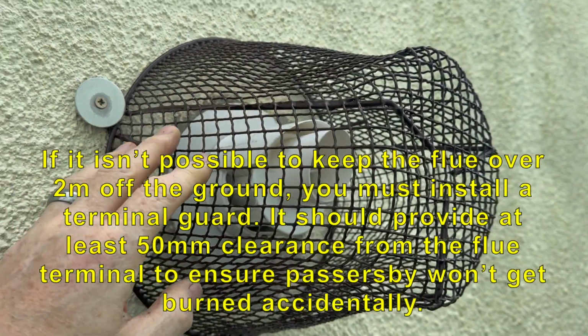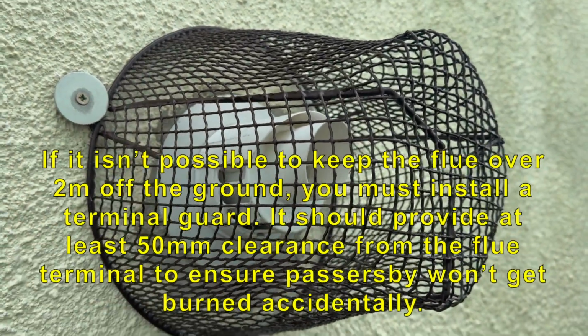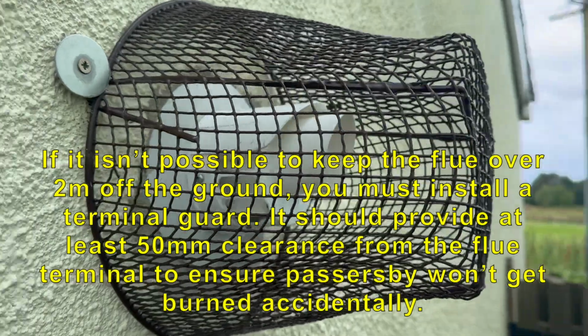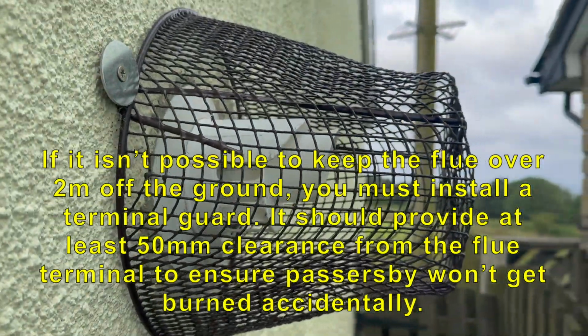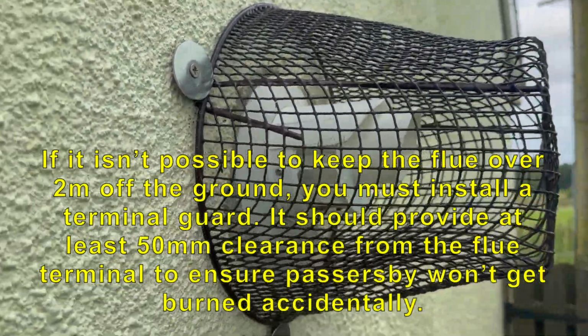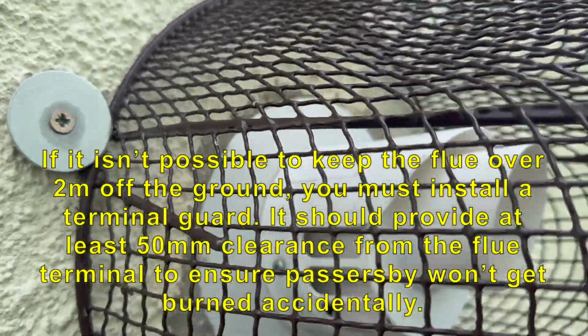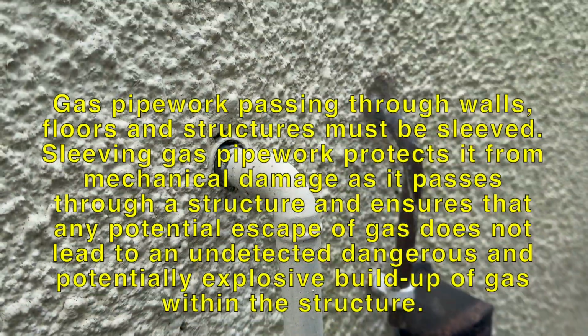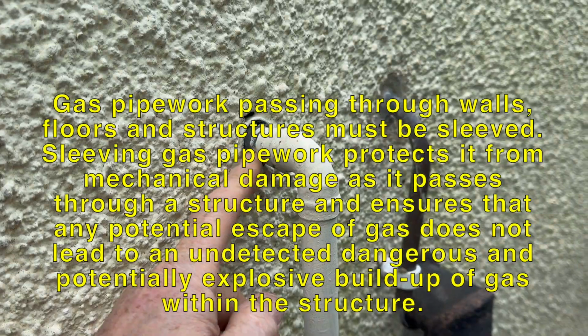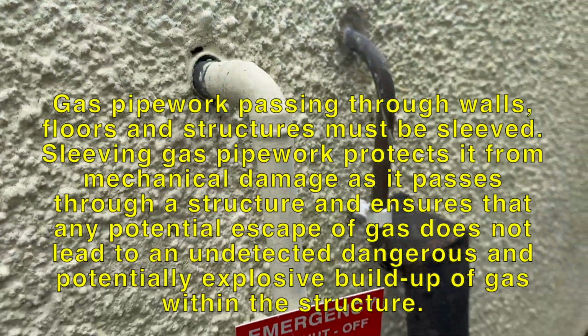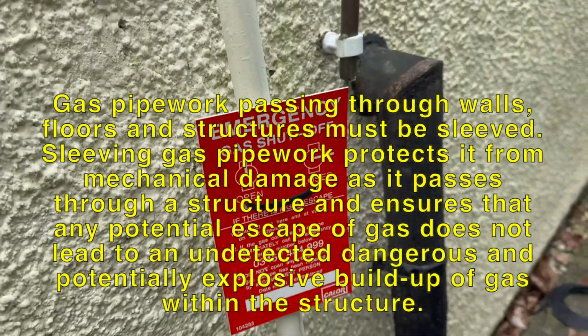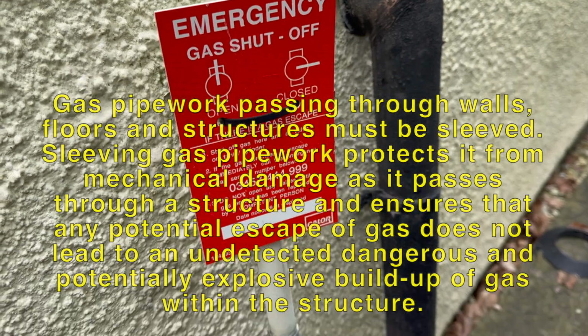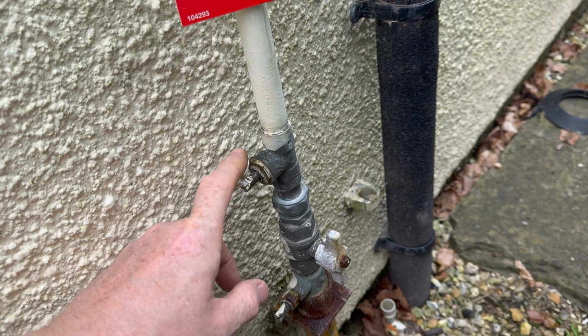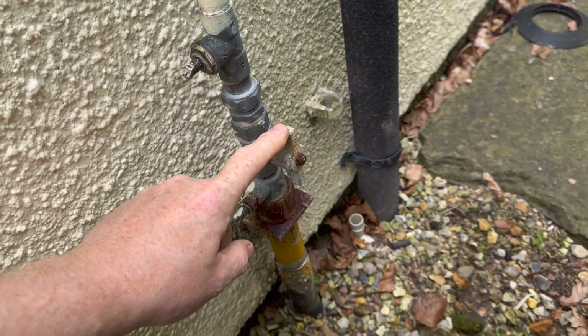Because the flue is installed less than 2 meters off the floor, we've got a cage, which the terminal guard seems to be installed correctly, and it does look like it's sealed on the outside. If we go down here, we can check the gas pipe. So it's sleeved and not sealed on the outside like it should be. We've got the emergency shut-off notice. We have a test point and ECV.